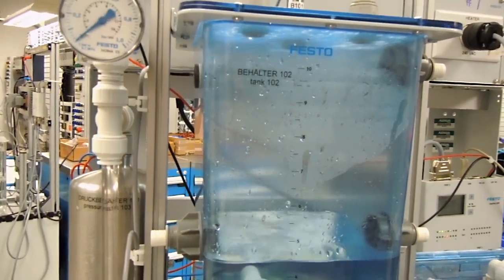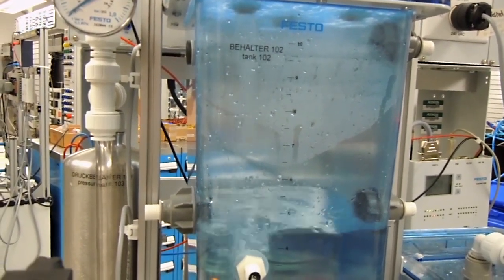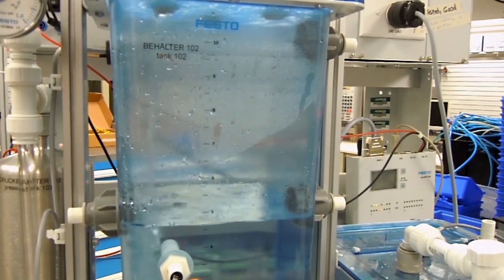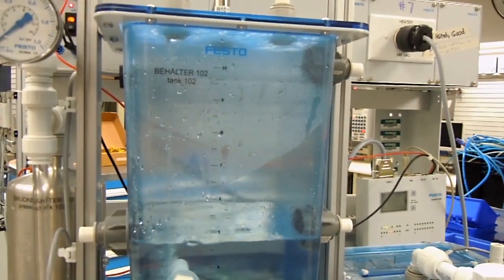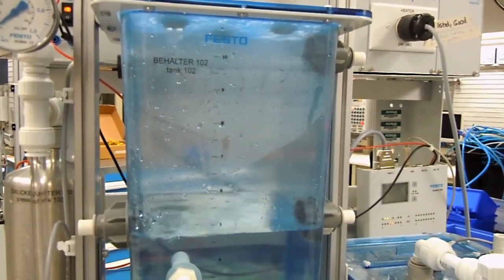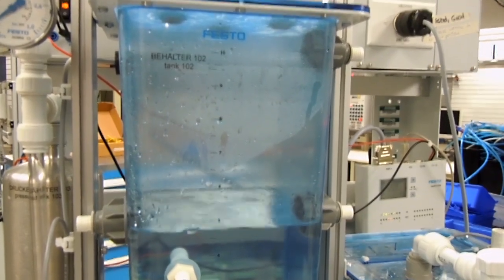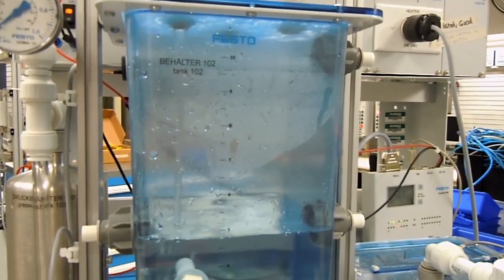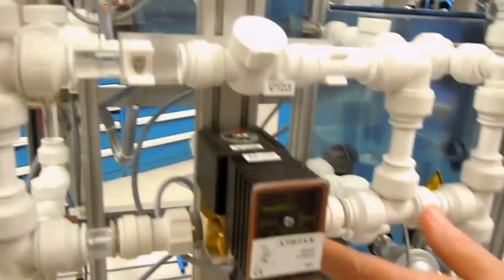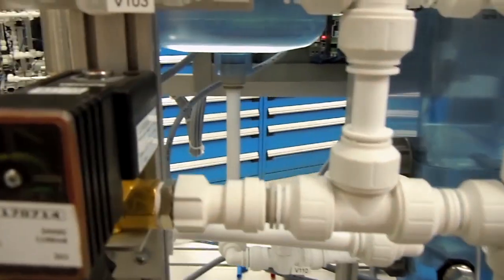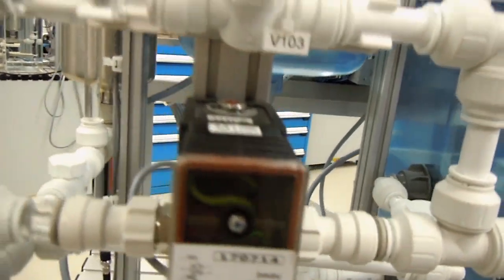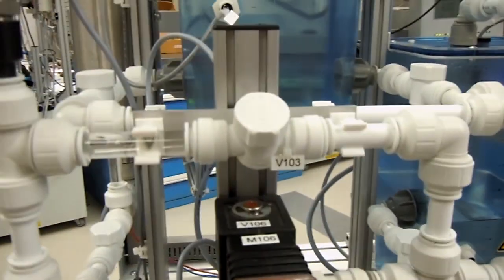So here's the valve at 10 volts, fully open, at about 5 volts, halfway, 2.5. So it's only about a quarter open now, and then fully closed. So moving that slider back and forth, I'm controlling how much liquid is flowing through this tube, proportionally. Okay? So that's the proportional valve.